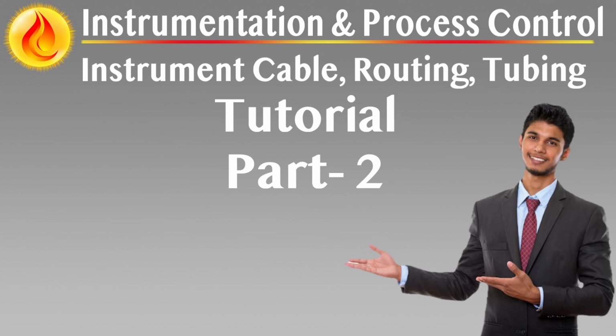In cases where the tubing serves instruments without an air supply, e.g. direct-acting control valves without boosters, the tubing must be rigidly clamped to a 25 mm dummy pipe or steel angle iron mounted to the structure, preventing sagging or accidental damage. All installation work must ensure proper bend radius, protect against kinks or crushing, and maintain accessibility for leak testing or replacement. Tubing routes should avoid hot surfaces, sharp edges, and potential impact zones, with additional mechanical shielding applied where necessary.